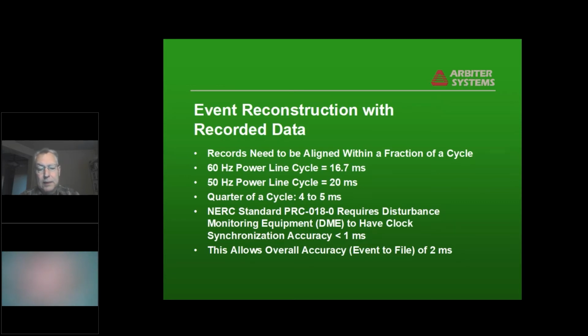And their standard PRC 018 requires 1 millisecond accuracy. That's of the clock in the IED that's doing the recording. And if there's 1 millisecond accuracy between all the devices, then they'll overall be accurate within 2 milliseconds of each other, which is about 1/8 of a cycle. And that's generally considered to be good enough for most applications.